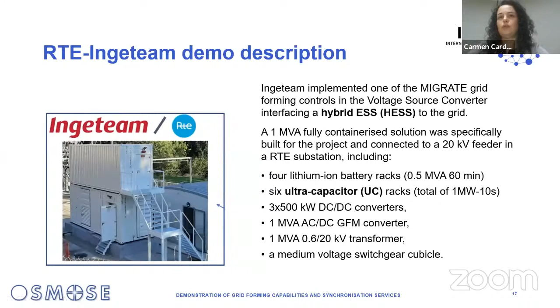We must say that this demonstrator could not be operated connected to the grid in the end, because we had an incident in the commissioning that prevented continuous operation within the time frame of the project. However, we did perform some interesting factory acceptance tests that I will let Markel present, which allow us to affirm that we have these contributions today in terms of control design. So for the grid forming control, we worked on two new things. The first was the inclusion of a negative sequence component in the threshold virtual impedance current limitation strategy, to improve grid forming robustness to asymmetrical faults.